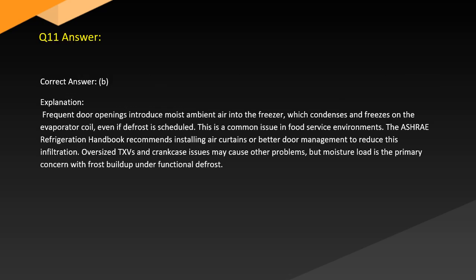Answer. Correct answer: B. Explanation. Frequent door openings introduce moist ambient air into the freezer, which condenses and freezes on the evaporator coil even if defrost is scheduled. This is a common issue in food service environments. The ASHRAE Refrigeration Handbook recommends installing air curtains or better door management to reduce this infiltration. Oversized TXVs and crankcase issues may cause other problems, but moisture load is the primary concern, with frost buildup under functional defrost.